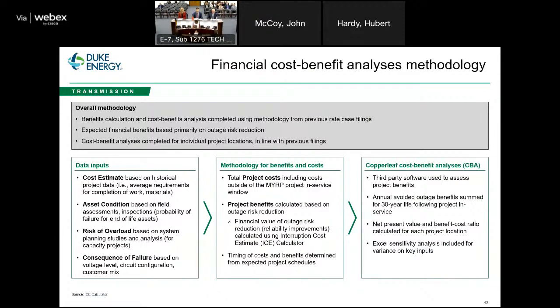The other part of the risk equation is consequence of failure. We rank that based on various factors, including voltage level - as a corollary for load, is this our 44 kV sub-transmission system or our 500 kV system? Is the load served by multiple sources, what we call networked, or is it a radial load with one source? And what is the customer mix - are we serving industrial, commercial, or residential customers from this transmission line? That factors in as well.